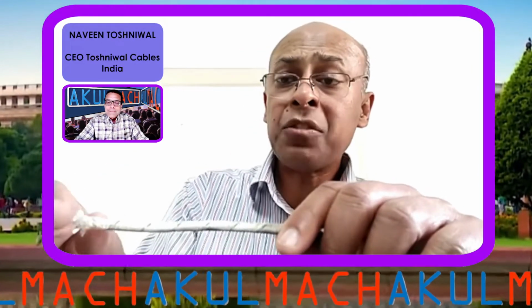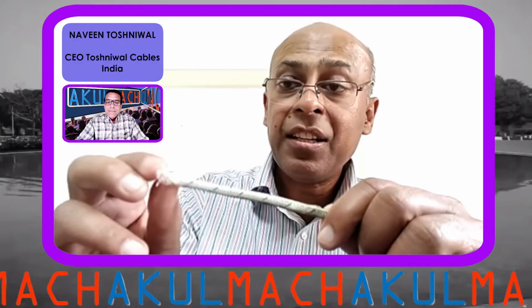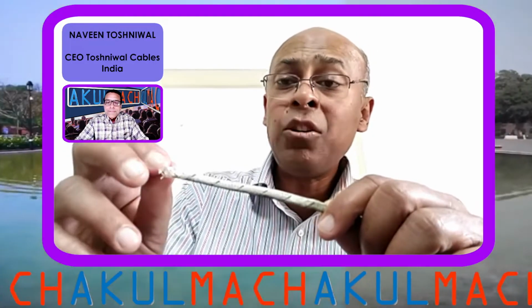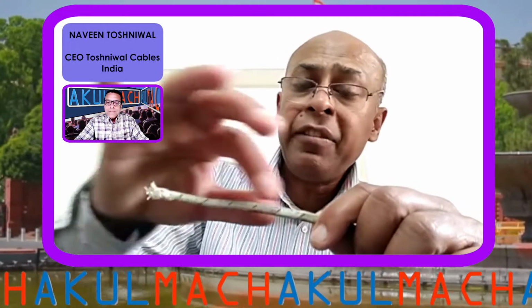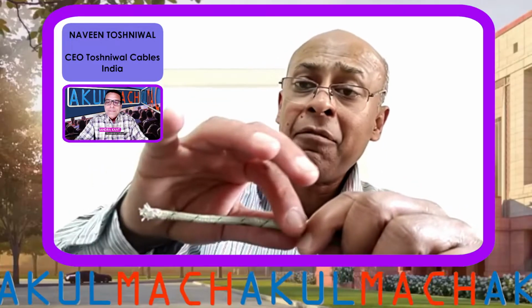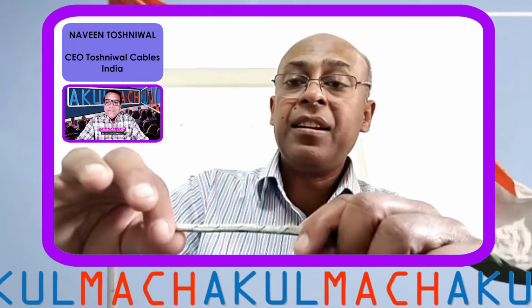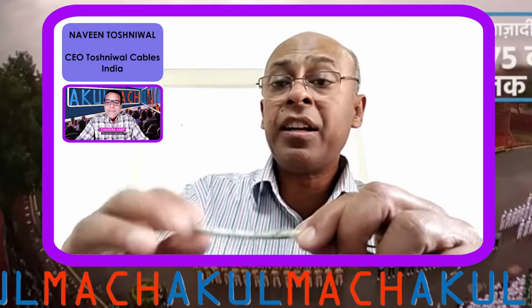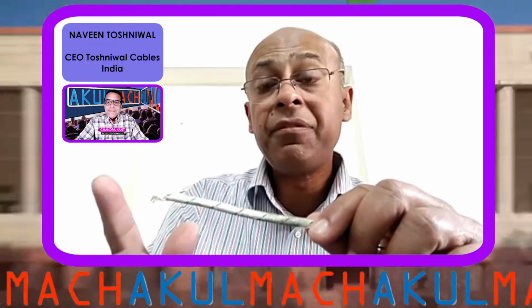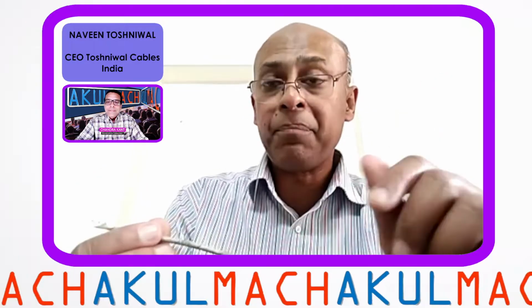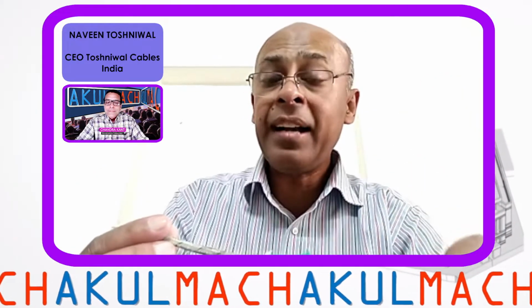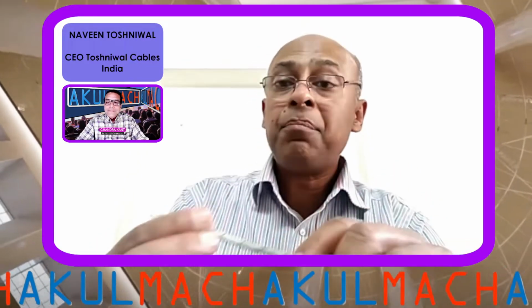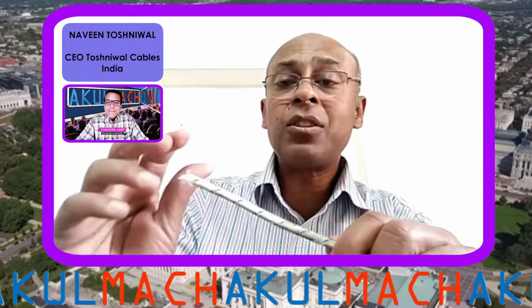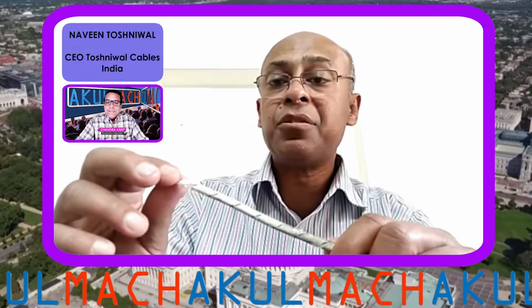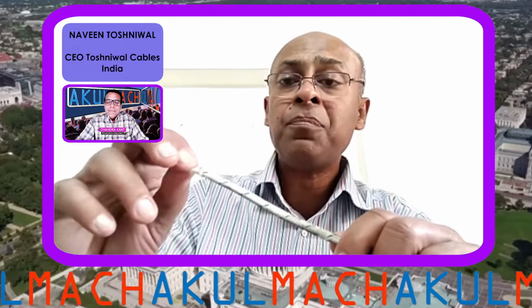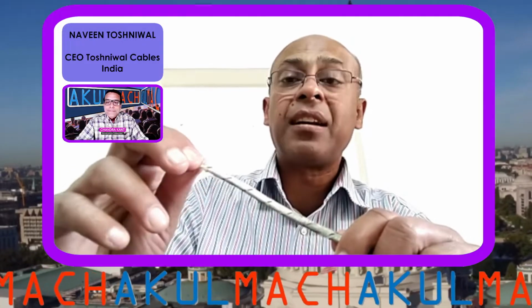Because fiberglass is in the form of yarns, it has fibres inside, so they will tend to break even if you pull it. So when we apply a varnish, it will become very sticky and stiff, and then high temperature varnish, if used, it can even withstand up to 350, even 400 degrees. So temperature wise, it is even having a higher temperature range than Teflon. But the only point is that this does not have any mechanical strength. It is very weak in the mechanical strength. So even if you pull it like this, the fiberglass strands will come out.